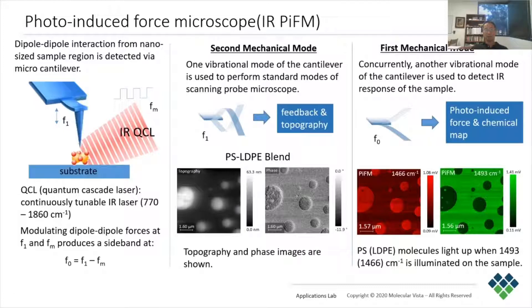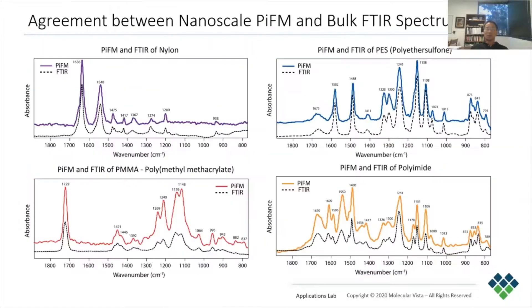At a fixed excitation wave number, PIFM generates a map of absorption strength for dielectric materials at that wave number. At a fixed location, the laser can be tuned across a spectral range to generate a PIFM spectrum, which correlates well with the bulk FTIR spectrum, provided the sample has no nanoscale inhomogeneity.